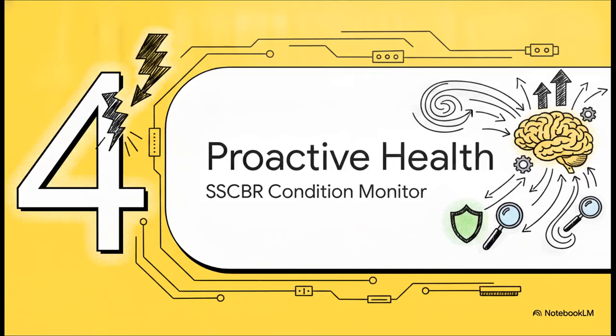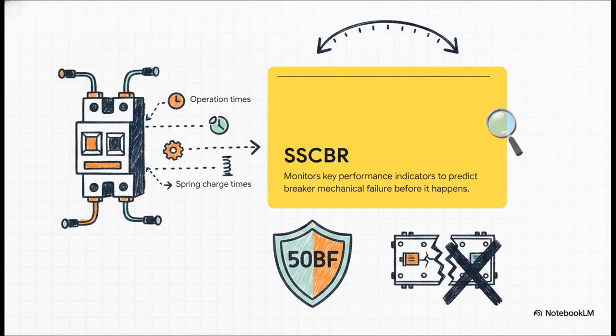All right, Section 4, Proactive Mechanical Health, SSCBR. But hey, what if we didn't have to wait for a catastrophic failure at all? This is where SSCBR comes in, which stands for Circuit Breaker Condition Monitoring. Instead of just waiting to catch a failed breaker during a fault, SSCBR monitors key performance indicators, things like operation times, wear, and spring charge times, to actually predict mechanical degradation before it happens. Its ultimate goal is to make sure our reactive 50BF safety net is never, ever forced into action.